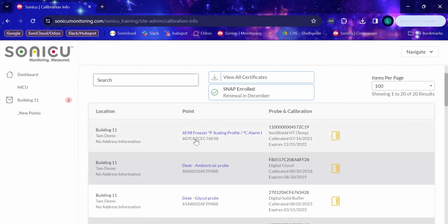Below that, you will have the serial number of the meter that the sensor is plugged into. And then off to the right, you have the serial number of the sensor and the type of sensor. So this is a SoniShield HT, which does temp and humidity, and this is letting you know it's the temperature side. It will tell you the date it was calibrated and the date it expires.